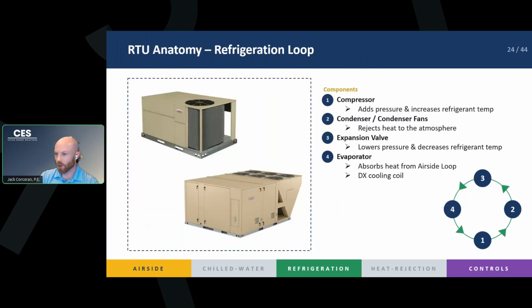So our four components: our compressor, condenser and condenser fans, expansion valve, and evaporator, right? We follow our loop. We go from hot to cold and high to low pressure. These are two rooftop units you can see on the left side. When you're looking at them, you can just tell that the one on the bottom is actually higher capacity because it has more condenser fans. That's what those fans on the top are.